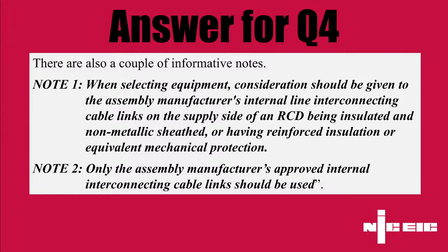But there are some manufacturers, I can't name them, but on their data sheets they will often refer to using a split load board, for example, on a TN system, and using an RCBO board referencing only for TTs. I've always wondered if that's a get-around, to be fair, because in the data sheets, some, not all, refer to what types of board and what type of earthing systems. So that's always an interesting one. But generally, on the whole, you're right. I've never known any cases of manufacturers to say you can't, but I am aware of one particular manufacturer that only refers to using their dual RCD boards on a TN system as opposed to a TT.